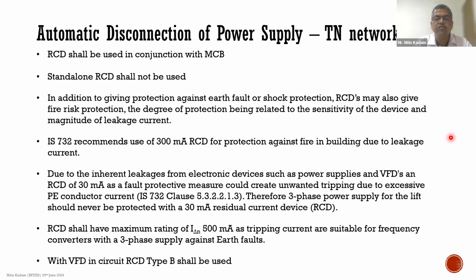So generally, the values of 300 milliamps or 500 milliamps are used based on the rating of the devices, and a type B RCD has to be used. As we have seen earlier, the type B RCD is the only RCD which is able to detect the AC leakage current, pulsating DC leakage current, high frequency currents, as well as the smooth DC current or the filtered DC current. This is the only RCD, and therefore RCD type B is a must. Please do not use any other RCD. RCD A or RCD AC is not to be used here.